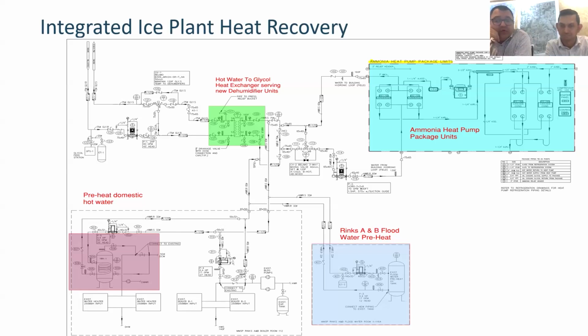Yes. So as part of our regular capital program, the dehumidifiers were due for life cycle replacement, and we wanted to build on that replacement based on the design studies that have been completed for the buildings, and move away from like-for-like replacement and implement energy efficiency measures. And as part of that process, we chose one of the multiple design options provided as part of the study, to replace the existing gas-fired dehumidifiers with new hydronic heating, and implement an ammonia heat pump, a heat recovery option on the existing ice plant. That will be the source for the dehumidifier. And that's how the project was implemented as part of the capital program, but including some carbon reduction options as part of our goal to achieve net zero by 2030.